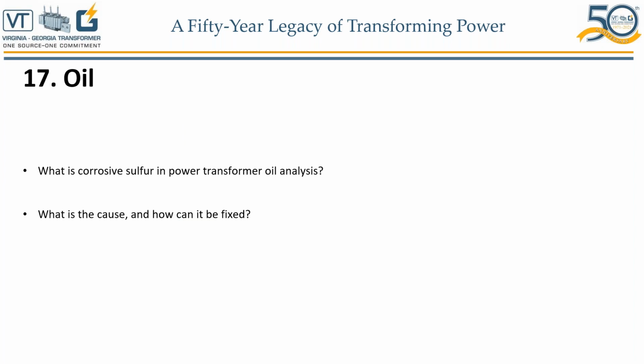What is corrosive sulfur in power transformer oil analysis? Let me answer what corrosive sulfur is first. There are different types of sulfur components found in refined transformer oil, but not all types are considered to be corrosive. Elemental sulfur and sulfur compounds in concentrations all the way up to 20% are present in the crude oil. There are 5 basic groups of sulfur and sulfur compounds found in crude oil, and the reason for that is that sulfur is 0.05% of the Earth's crust. Some sulfur compounds can actually aid in the oxidation of the oil, and some can act as metal passivators and deactivators, reducing the catalytic effect of oil oxidation.